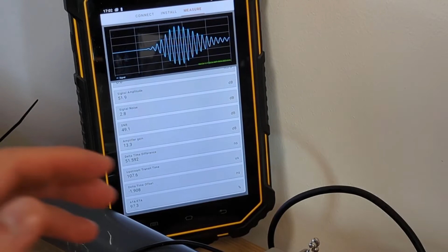To improve percent of the signal, you could adjust the sensor position a little bit. Here, I pushed one sensor closer, and you can see the ATA-ETA improve after that's been done. It's now gone to 98%. Give it a few seconds for it to stabilize. Once you're happy with the ATA-ETA and the shape of the waveform, you can scroll up to view your measurement.